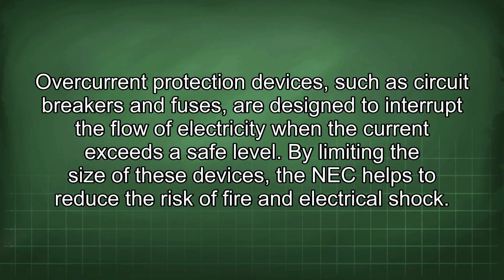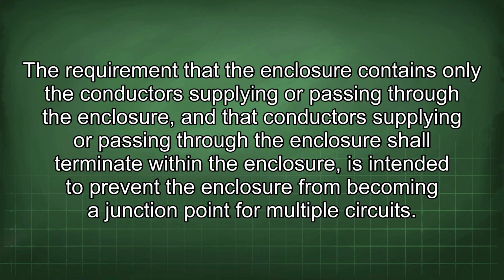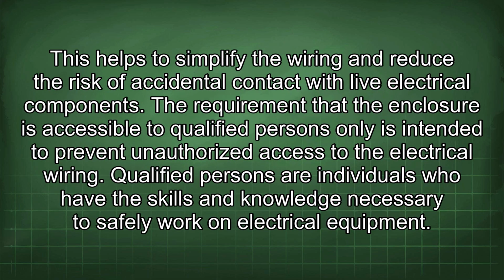The requirement that the enclosure contains only the conductors supplying or passing through the enclosure, and that conductors supplying or passing through the enclosure shall terminate within the enclosure, is intended to prevent the enclosure from becoming a junction point for multiple circuits. This helps to simplify the wiring and reduce the risk of accidental contact with live electrical components.